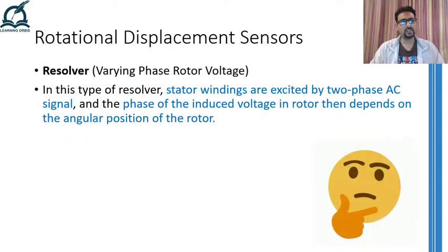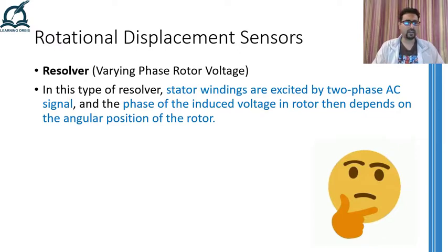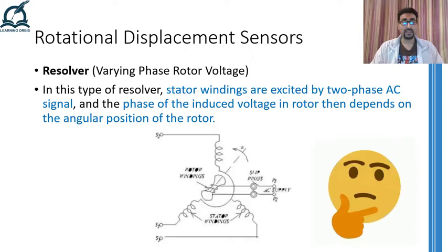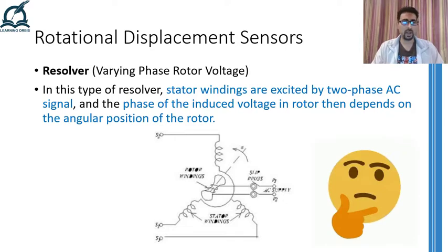In the varying phase rotor voltage form, instead of the rotor, the stator windings are energized with different phase AC signals. If the rotor is facing the sine stator winding, sine voltage is induced in the rotor; if it is facing the cosine stator winding, cosine voltage is induced. The phase of the induced voltage depends on the angular position of the rotor. Devices similar to resolvers but incorporating three stator windings are called synchros. They have a similar working principle but provide better resolution because of the three stator windings.